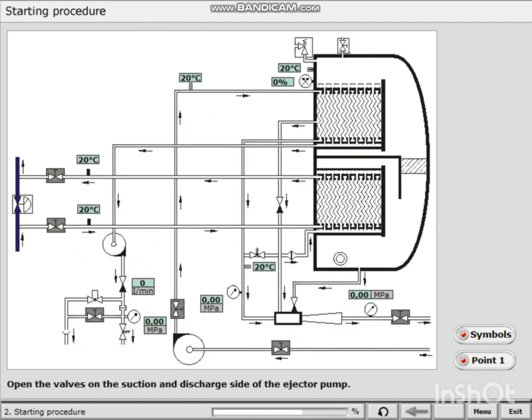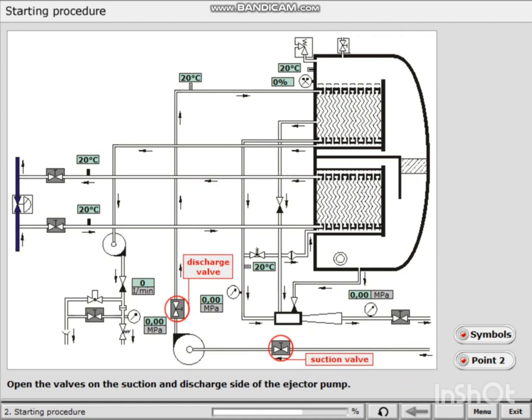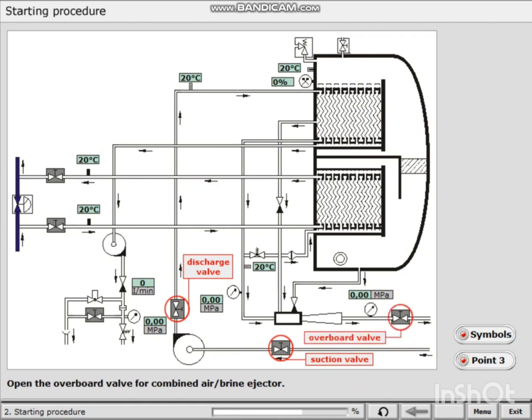Open the valves on the suction and discharge side of the ejector pump. Open the overboard valve for combined air brine ejector. Close the air valve on the upper part of the separator vessel.